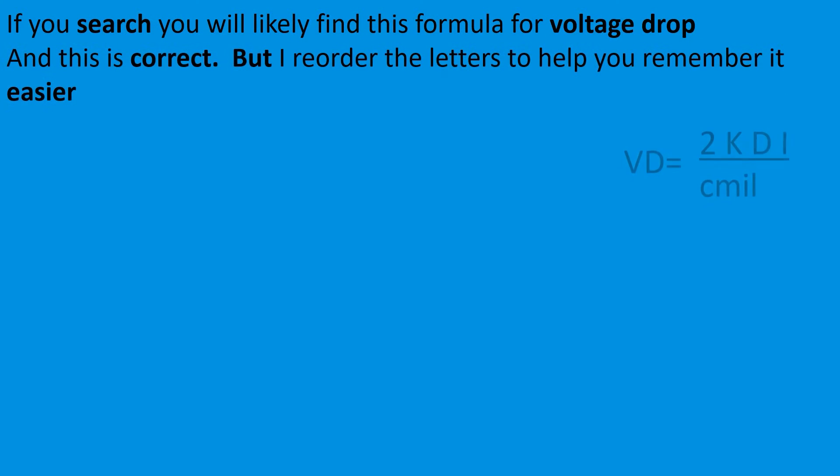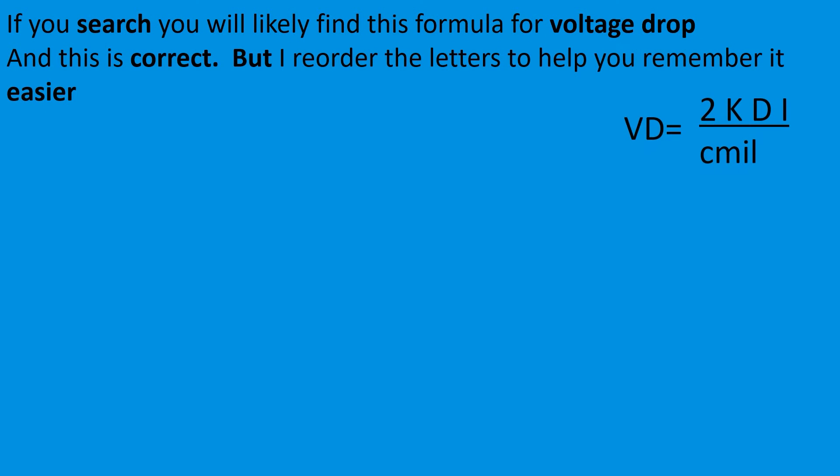Okay guys, if you do an internet search, you'll likely find this formula for voltage drop right here. And this is correct, but I've reordered the letters to help you remember it easier. If you get this, you'll have this for the rest of your life. This is how I order it. It's the same equation. It's voltage drop equals 2KID over cmil. And we're going to break all this down here in the next few slides.